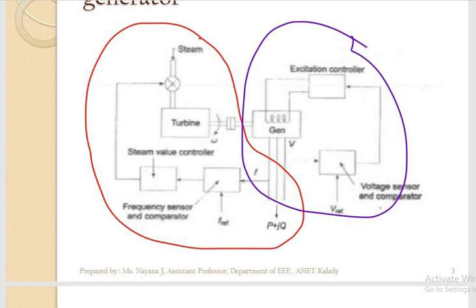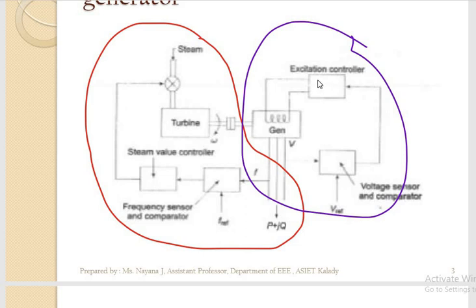What do we mean by excitation of a generator? For a generator to work, it should have a magnetic field. That magnetic field is provided by the field winding, and for providing the magnetic field, that field winding needs to be connected to a DC supply. For that we use an exciter. So that magnetic field is provided with the help of an exciter. By controlling that exciter voltage, the magnetic field is controlled and indirectly the output voltage is also controlled. So to control the output voltage of the generator, we control the exciter voltage.